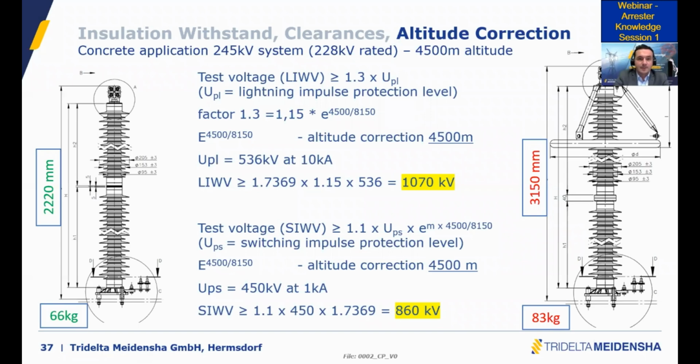So always refer to the residual voltage, and don't specify arcing distance for such arrestors. But you have to mention the altitude, and you have to make sure that the manufacturer guarantees the performance with this altitude.